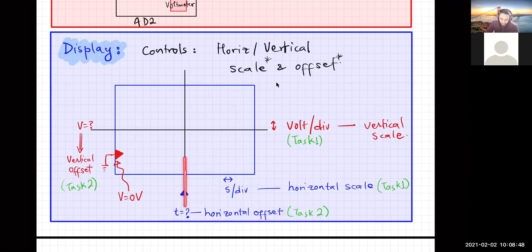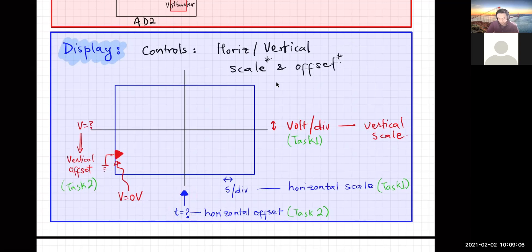Horizontal offset means what time value corresponds to the center of the screen. The question of where time equals zero is somewhat ambiguous, and we'll come back to horizontal position when we talk about triggering.